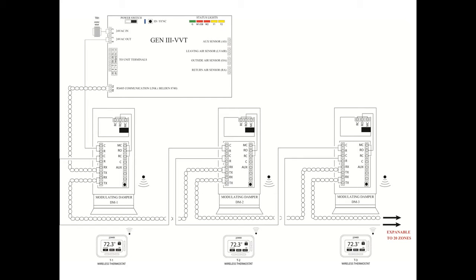The control wiring from a GenIII controller to each communicating damper board is the key to effective communication and operation. From the RX TX terminals on the controller, pull a 2-wire, unshielded twisted pair communications loop, daisy chained damper to damper. We utilize and specify Belden 8740, which is a 22 gauge wire.